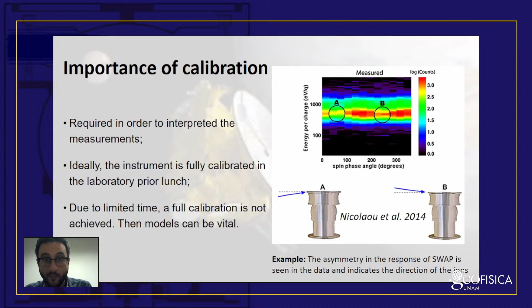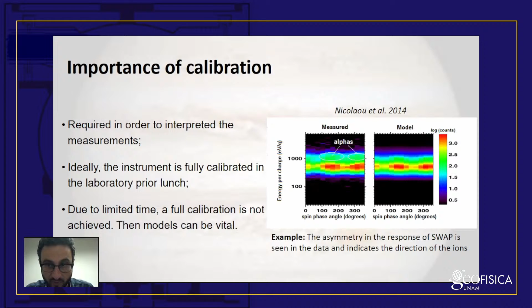So here you have the measurement. You have an energy spin angle matrix as measured from this instrument. And here you have the model after taking into account the calibration. And you see that the asymmetry is characterized quite well. And that was the only way to understand where the actual flow of ions is going. So in this publication here, we resolve the motion of the Jovian magnetotail as a response to solar wind. And that would not be possible if we did not look at the calibration of the instrument and understand and analyze the data properly.